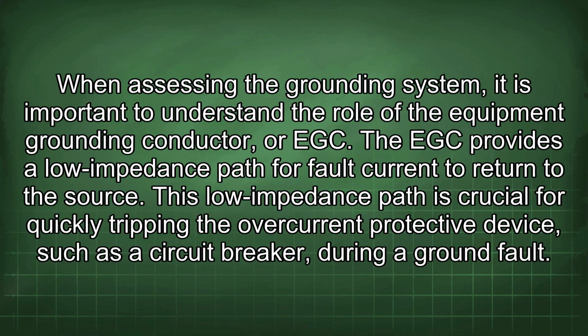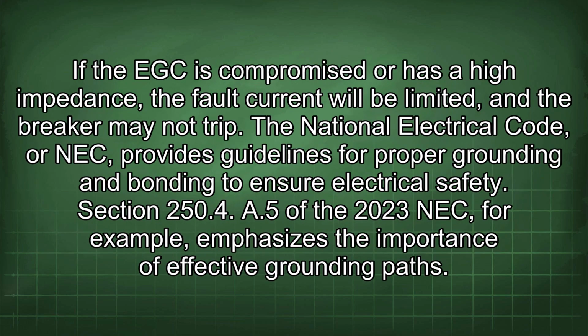When assessing the grounding system, it is important to understand the role of the equipment grounding conductor, or EGC. The EGC provides a low impedance path for fault current to return to the source. This low impedance path is crucial for quickly tripping the overcurrent protective device, such as a circuit breaker, during a ground fault. If the EGC is compromised or has a high impedance, the fault current will be limited, and the breaker may not trip.